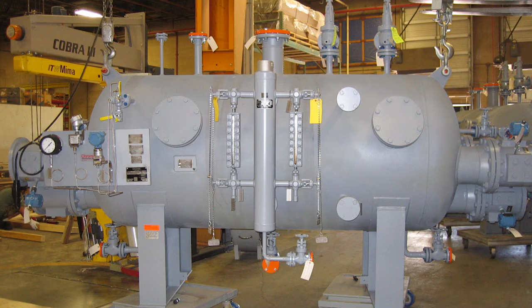Heat transfer systems—the case study we gave you was actually a hot oil system at a refinery. Hot oil systems are typically getting larger and larger in scope, so moving that to electric is a really good option, especially if facilities are at their permitting or emissions levels and can't add more without going through that process. It's a great addition for new capacity and new systems needed in the plant.